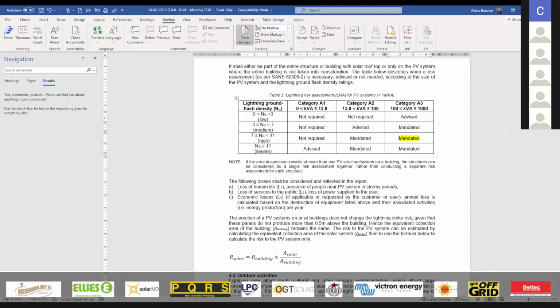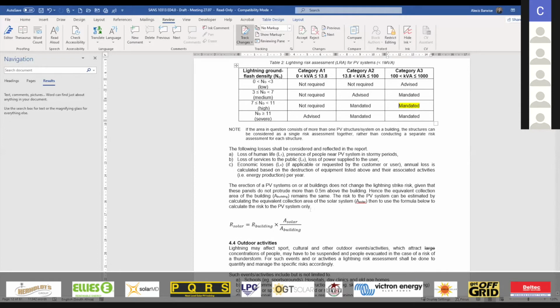What we know is that buildings themselves have to have done a lightning risk assessment based on the 62305 standard part 2, where they've already ascertained risks like occupant and human life risk for the mall. If the customer has done that assessment and we have those values, a nice way to obtain the solar risk is to say it equals the building's risk assessment multiplied by the area the solar takes up relative to the building's total area.